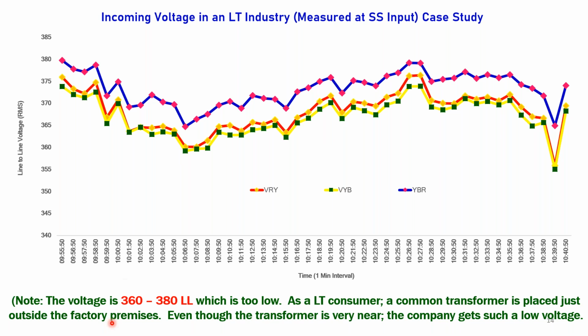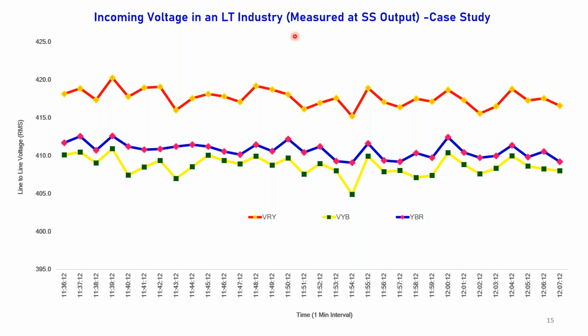But during our measurement, we found that the input voltage is going to be higher. That is not a problem. But see the output of the servo stabilizer. As you know, the servo stabilizer maintains a constant voltage at the desired set level. Now this is the voltage we measured at the servo stabilizer for nearly 1 hour. We measured more than 1 hour, but I'm just giving only a half-hour slot here.